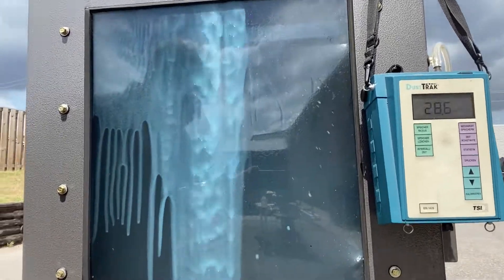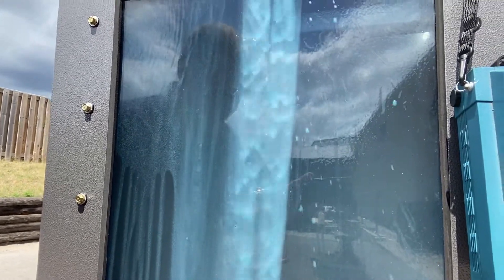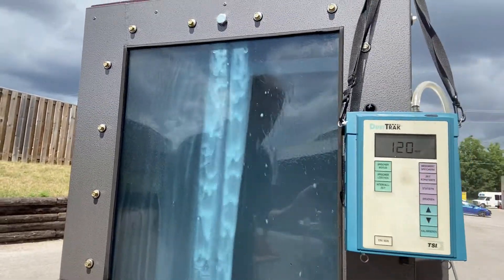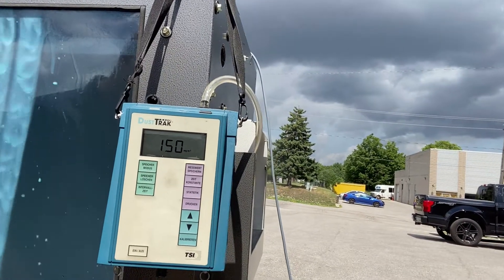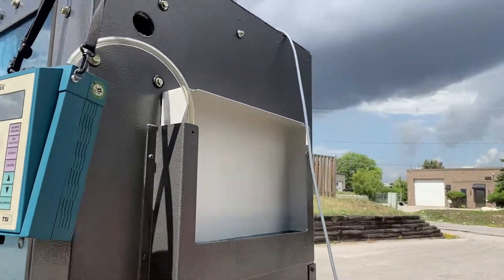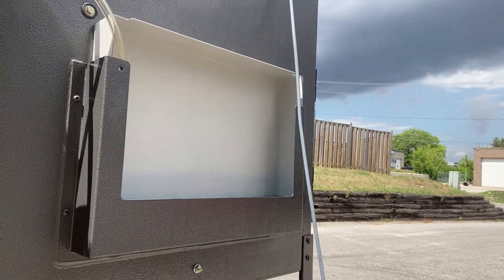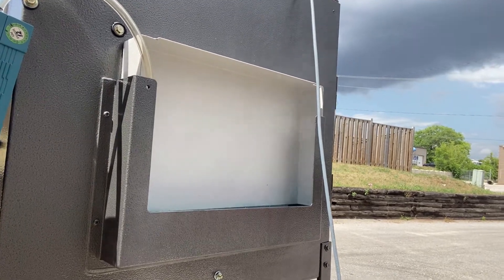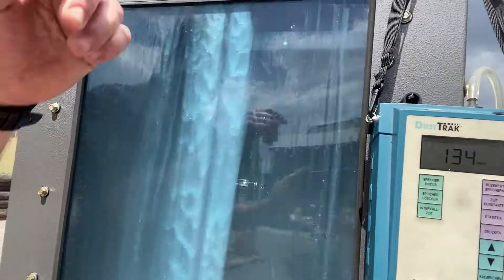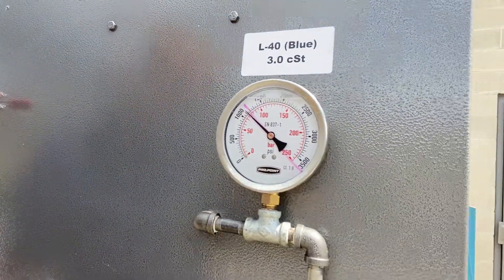And it begins. So you can see the action going on in there now — absolute chaos. The DustTrak is climbing to above 100 milligrams per cubic meter. You can see the mist filing out of our test tank here, and this is the mist that would be contaminating the air in your facility. The pressure right now is at 1200 psi.